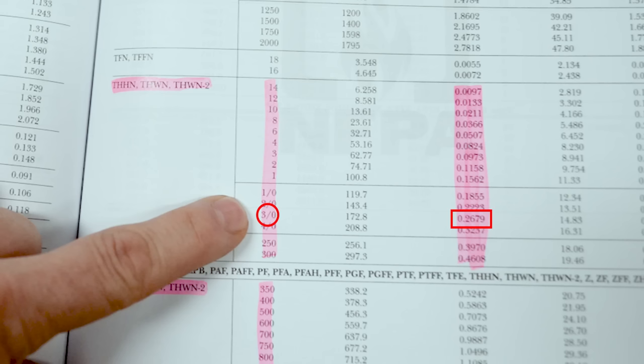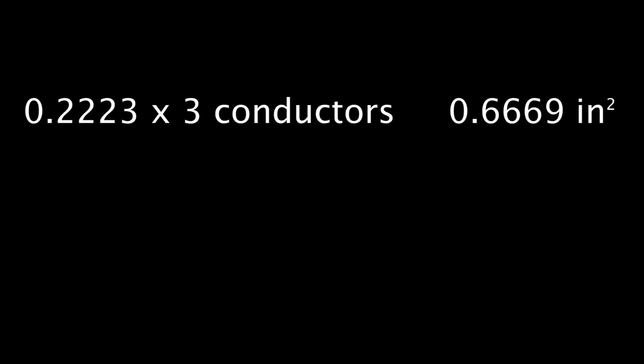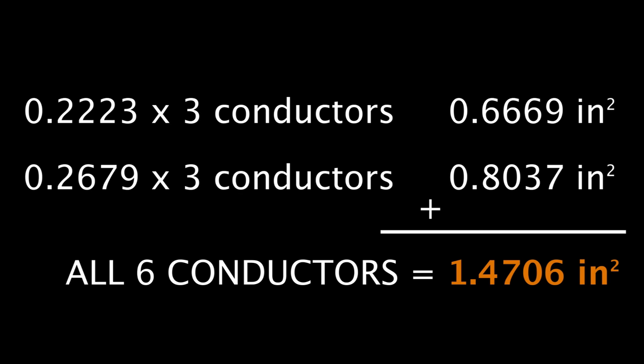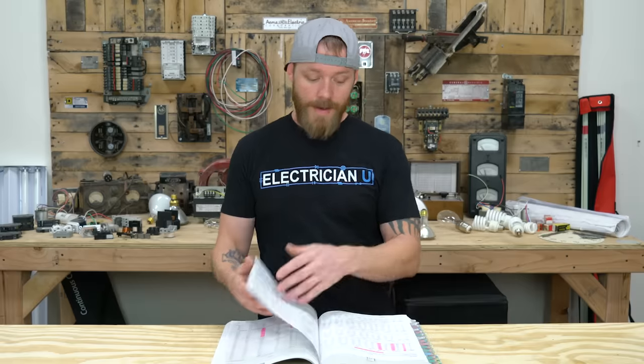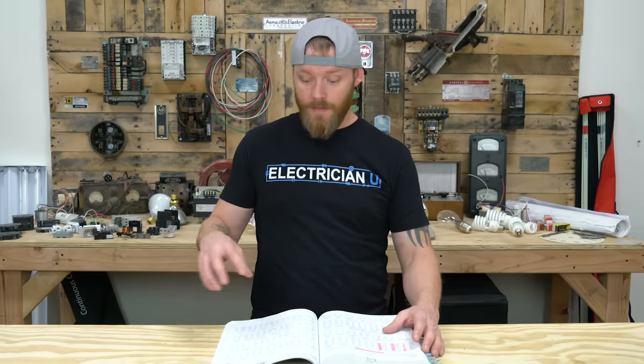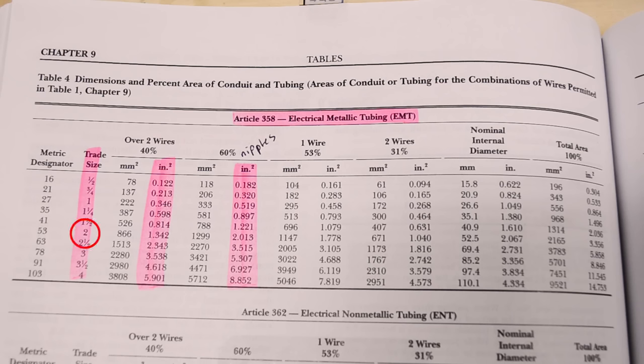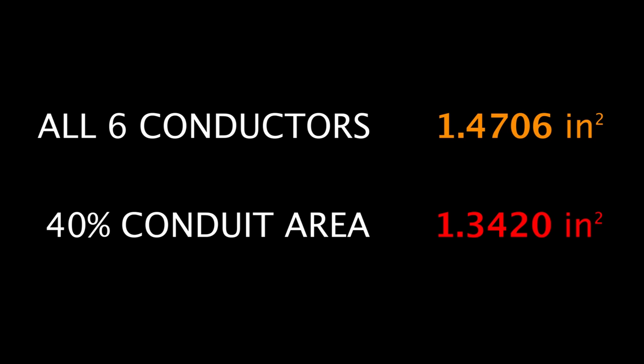Now multiply each of those values by 3, since we have three 2-aught conductors and three 3-aught conductors. All together that equals 1.4706. Then go to table 4, look at 2-inch EMT, go over to the 40% column under inches squared, and 2-inch says 1.342. So no — those conductors will not fit per code. They may fit if you cram them in, but to code you're not supposed to put those in there.